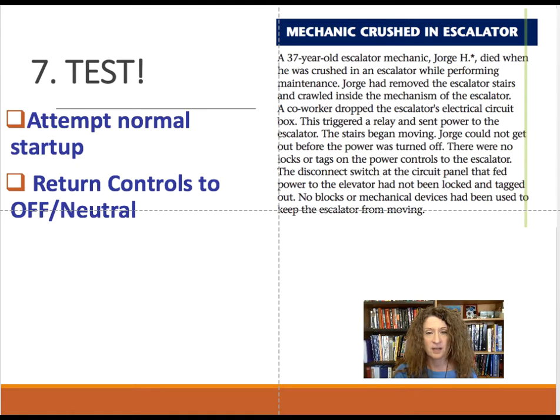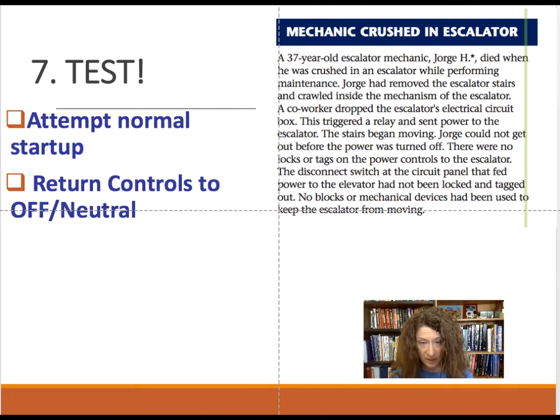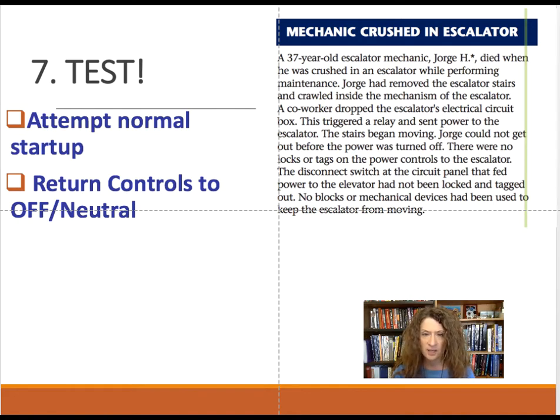Step 7: After lockout-tagout, actually test the equipment — try to turn it back on and see whether the system will energize. Hit the on button a couple of times; if you've isolated all the energy, the system won't turn on. A case study: a 37-year-old escalator mechanic named George was crushed in an escalator while performing maintenance. He had removed the stairs and crawled inside the mechanism. A co-worker dropped the electrical circuit box, triggering a relay that sent power to the escalator. The stairs began moving and George could not get out. There were no locks or tags on the power controls, and the disconnect switch had not been locked or tagged out.